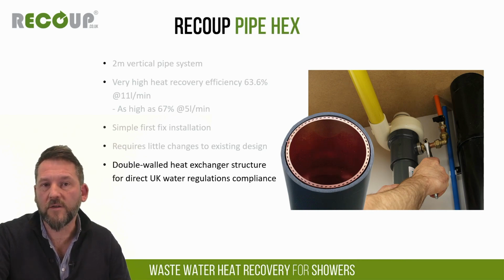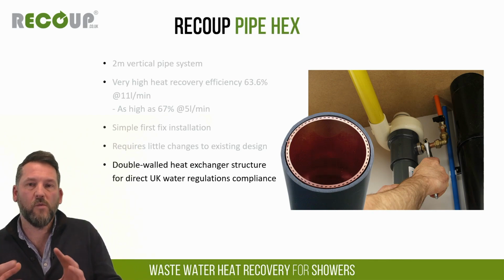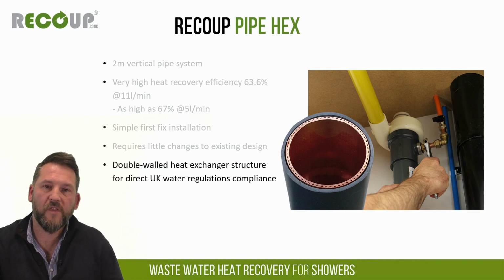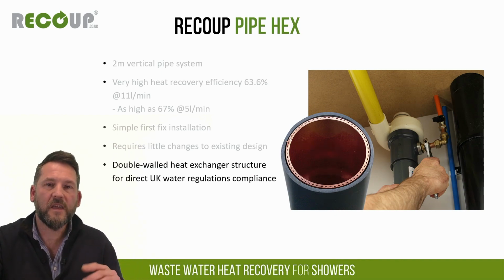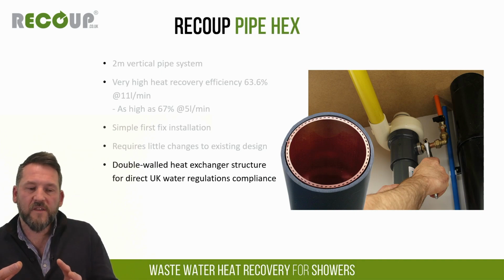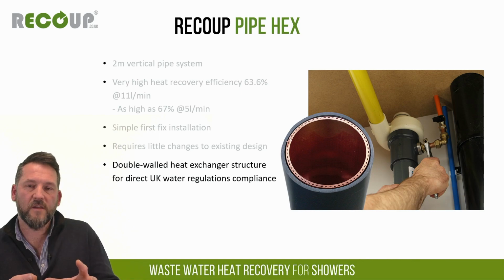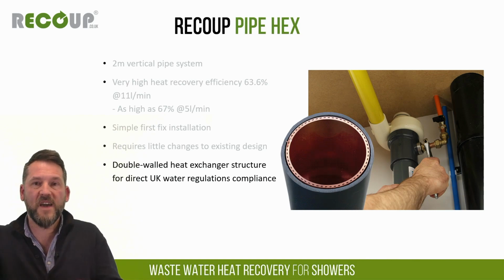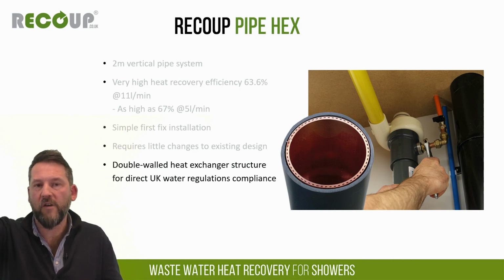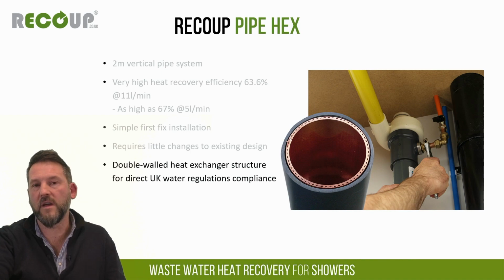And then the eagle-eyed amongst you will see that there are actually striations or marks running around the middle of the heat exchanger here. All Recoup products use a double-walled heat exchanger system. So this is a mechanically pulled pipe through a pipe, and these striations run the entire length of the copper heat exchanger. What it does, it gives us a visible leak detection system, which is a belts and braces approach to water regulation compliance. It means in practice that with a visible leak detection system in place, the shower trap can remain upstream of the wastewater heat recovery underneath the shower where it belongs, rather than having to come downstream of the unit, which potentially causes issues in terms of installation height and accessibility and things.